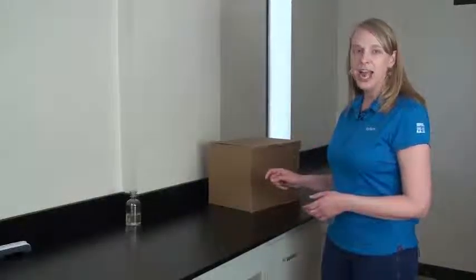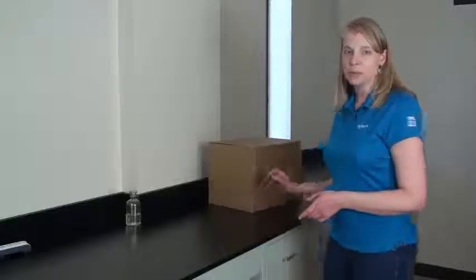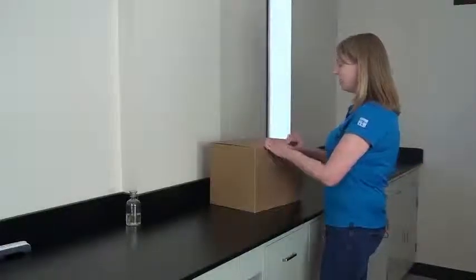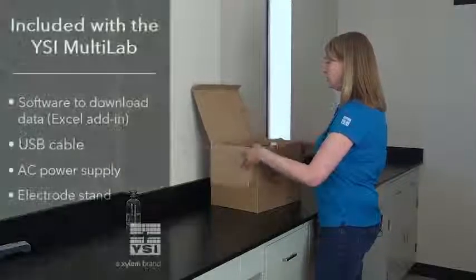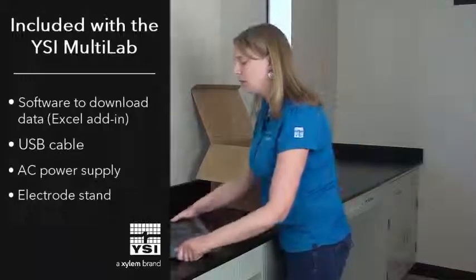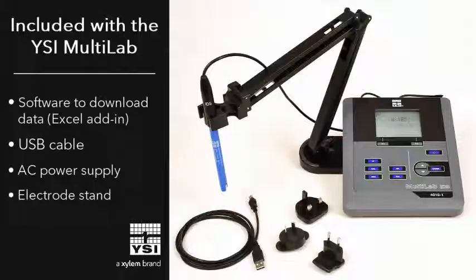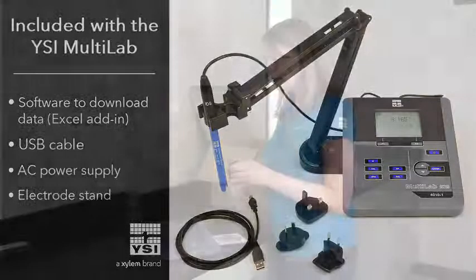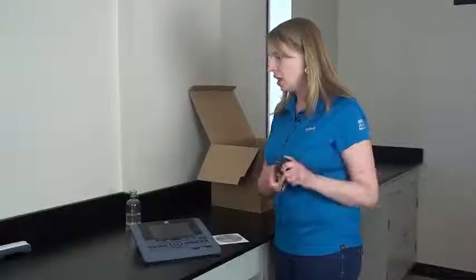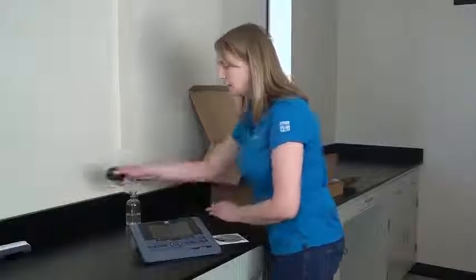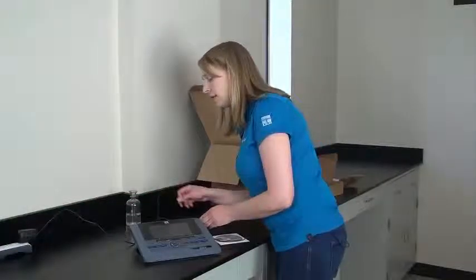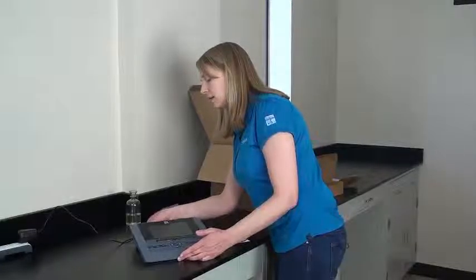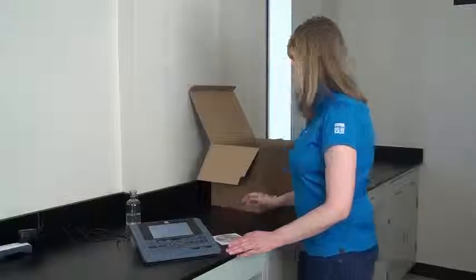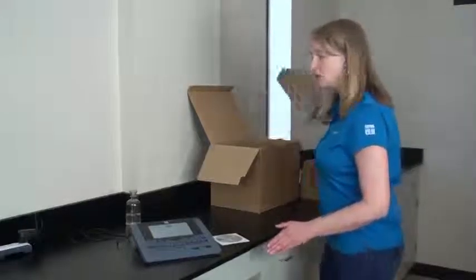Right now, I will demonstrate how to get the MultiLab meter ready for your measurements. Today, I'm going to demonstrate the 3-channel version. All MultiLab instruments include the software for downloading data to Excel and an AC power supply, as well as an electrode stand. The instrument is digital and automatically recognizes when a sensor is connected. So as I power this up, you'll see the instrument request for a probe because it automatically recognizes that there's no probe connected.